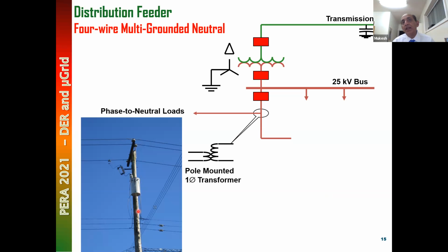Actually, the neutral is in the center, and it's a 120 plus 120 transformer, a two-phase, single phase one. There's 120 here, 120 here, and the center is a neutral. So it's going to two houses, A house and B house, like that. So this is a single phase transformer with a center neutral, 120 volt to 120 volt, connected to single phase. It is a pole-mounted transformer, with phase to ground voltage here.